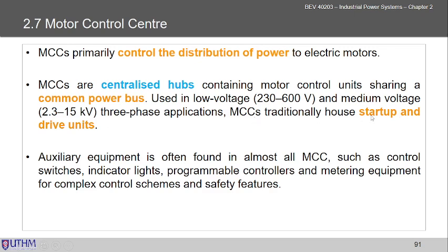The function of the MCC is normally to start up the motors, that means to start up individual motors. In the MCC itself, they have a lot of starting circuits for individual motors. And the drive could drive a group of motors. So they have a lot of auxiliary equipment in the MCC. Remember, you have the control switch, the indicator light, the programmable controller, the PLC, and the metering equipment, for example, etc.